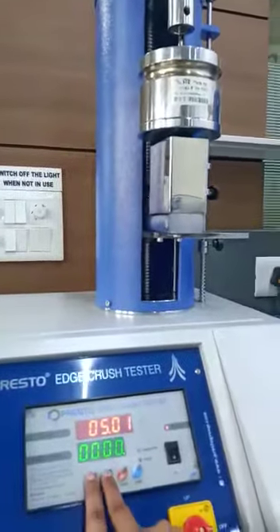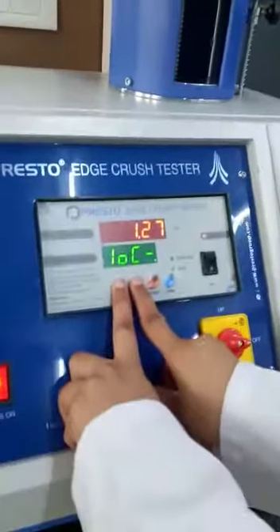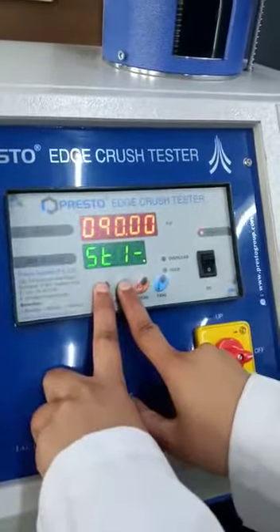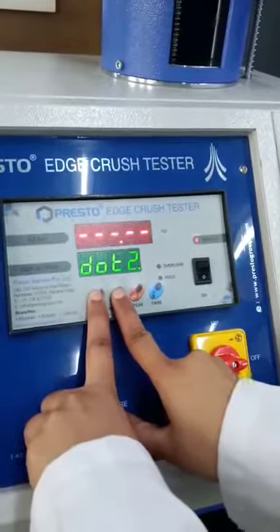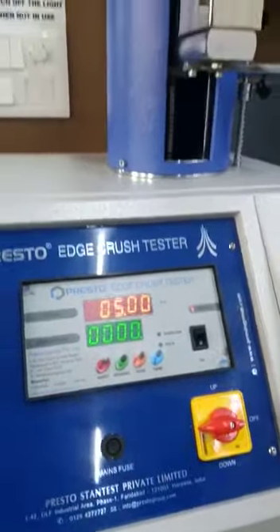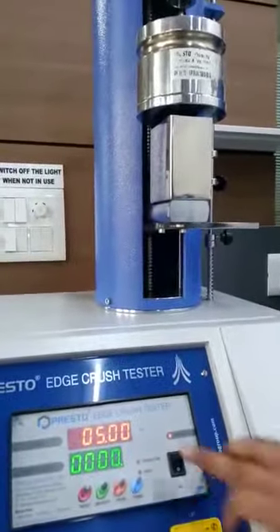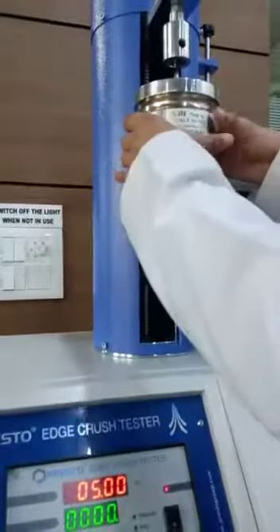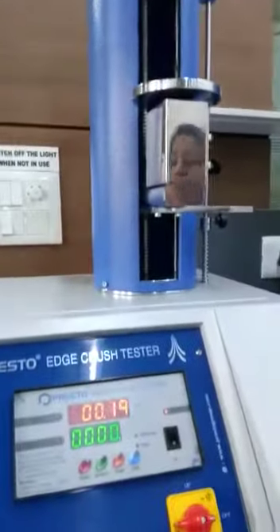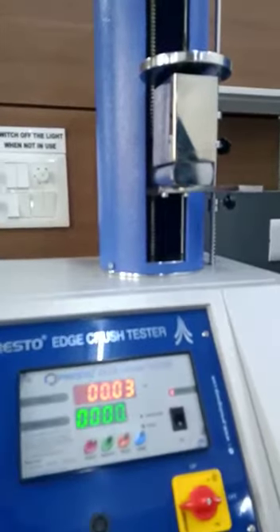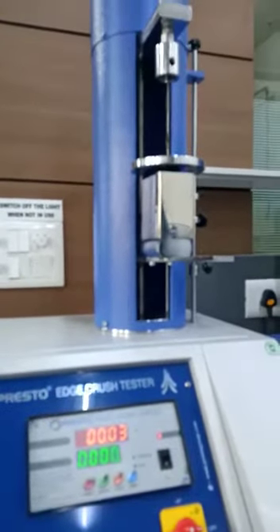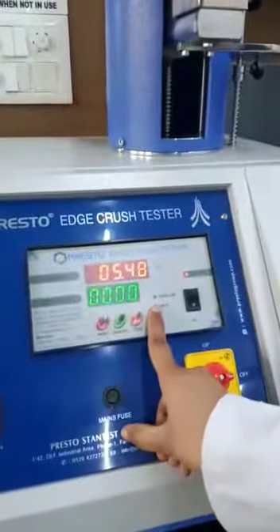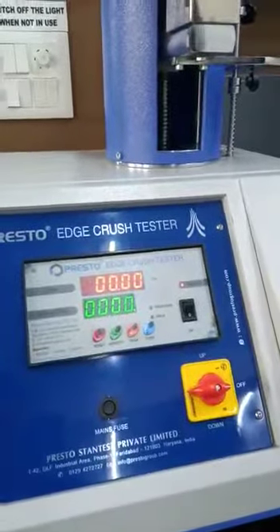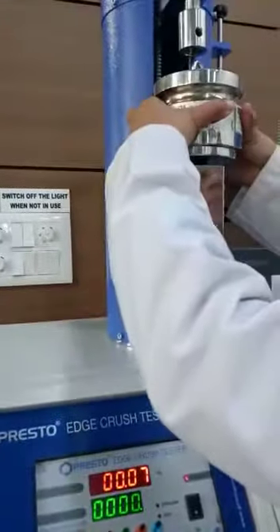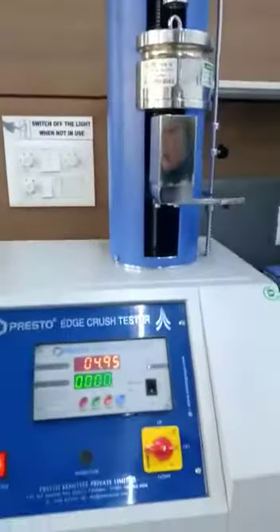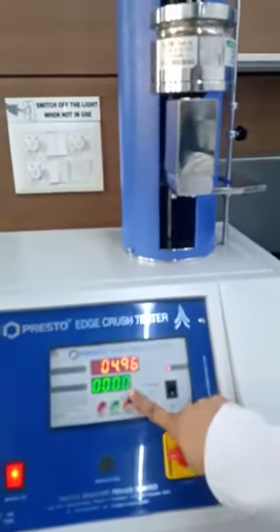Then again press reset and memory together again. So this is the same value. You can also verify the same. Remove the weight, then the load indicator will read 0. Then press reset. Then again apply weight, and it will show the same value of load.